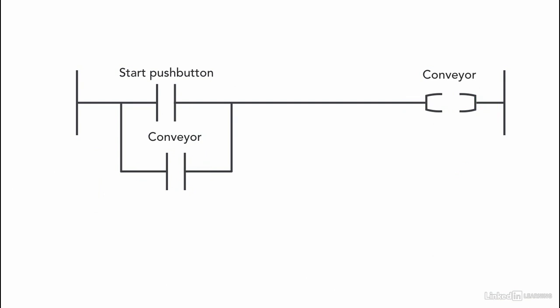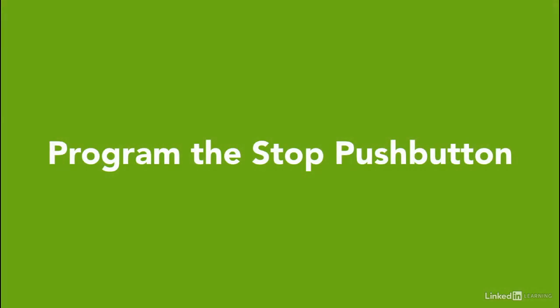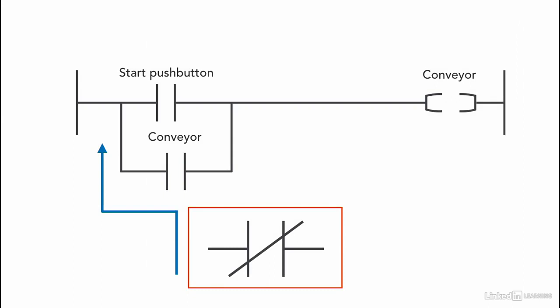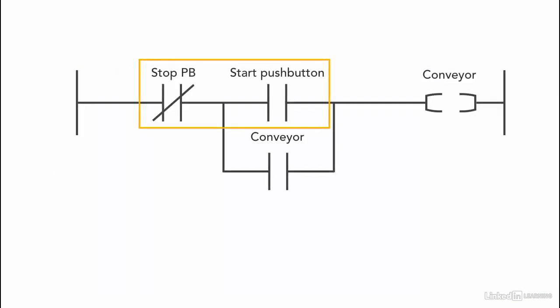Now we need to program the stop push button so that the conveyor stops when it is pressed. Since we're using a normally open contact for the stop push button, we are going to use an XIO instruction to keep continuity, and we add it in series with the start push button. In the normal situation, the stop push button is not pressed — it's a normally open contact, so the memory location equals zero. When using an XIO instruction, the instruction is highlighted when the memory location is zero, so it's highlighted without needing to press the stop push button, and that's what we need, because the stop is only pressed when we want to stop the conveyor.